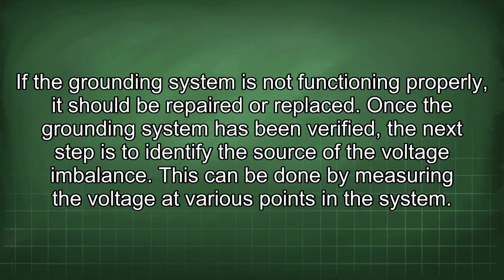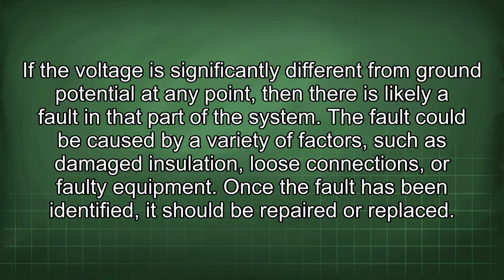Once the grounding system has been verified, the next step is to identify the source of the voltage imbalance. This can be done by measuring the voltage at various points in the system. If the voltage is significantly different from ground potential at any point, then there is likely a fault in that part of the system. The fault could be caused by a variety of factors, such as damaged insulation, loose connections, or faulty equipment. Once the fault has been identified, it should be repaired or replaced.